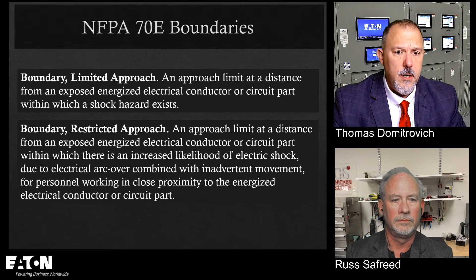One of the things to remember from a hazard perspective is 110.4C and 130.1. 110.4 is your energized work, and C talks about energized electrical conductors. So it's equipment operating at less than 50 volts. Energized electrical conductors and circuit parts that operate at less than 50 volts shall not be required to be de-energized where the capacity of the source and any overcurrent protection between the energy source and the worker are considered, and it is determined that there will be no increased exposure to electrical burns or to explosion due to electric arcs. So I don't have an arc flash hazard at less than 50 volts, and I don't have a shock hazard at less than 50 volts.